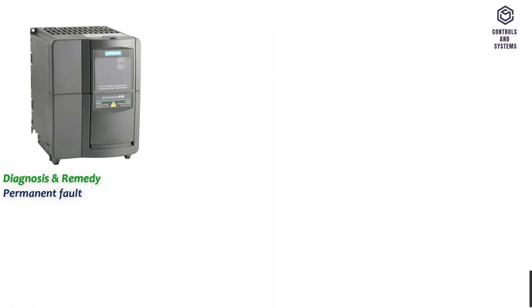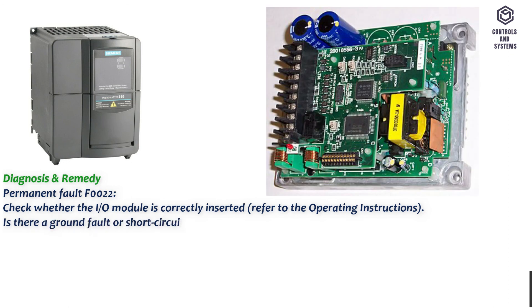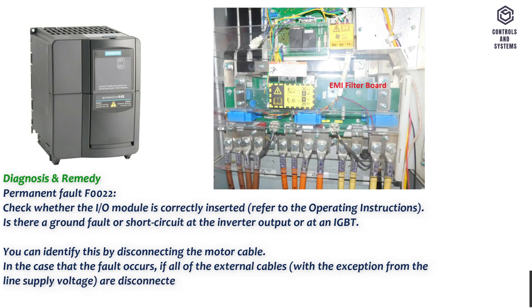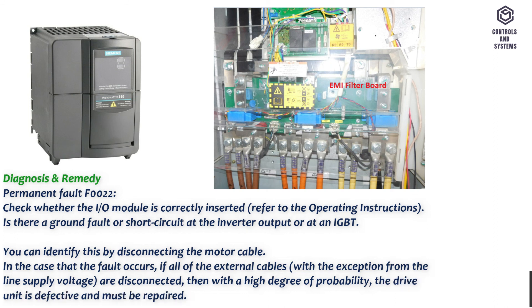Permanent fault F0022: Check whether the IO module is correctly inserted, refer to the operating instructions. Is there a ground fault or short circuit at the inverter output or at an IGBT? You can identify this by disconnecting the motor cable. In the case that the fault occurs if all of the external cables, with the exception of the line supply voltage, are disconnected, then with a high degree of probability the drive unit is defective and must be repaired.